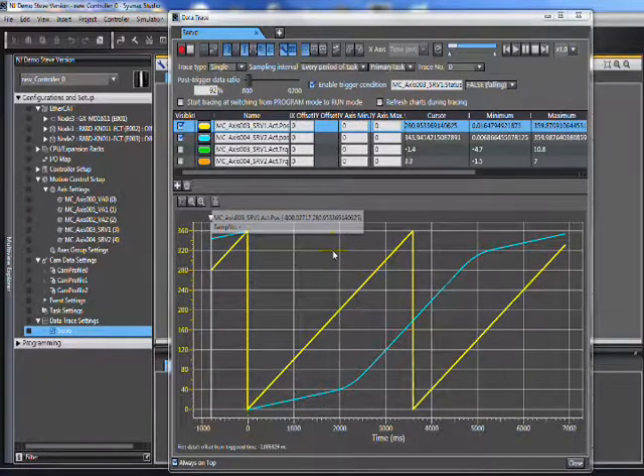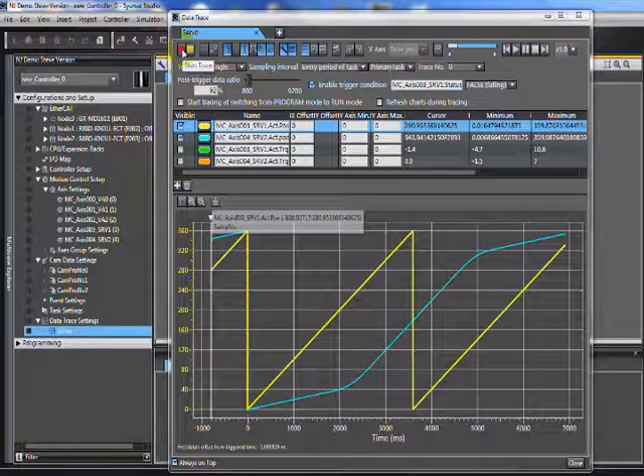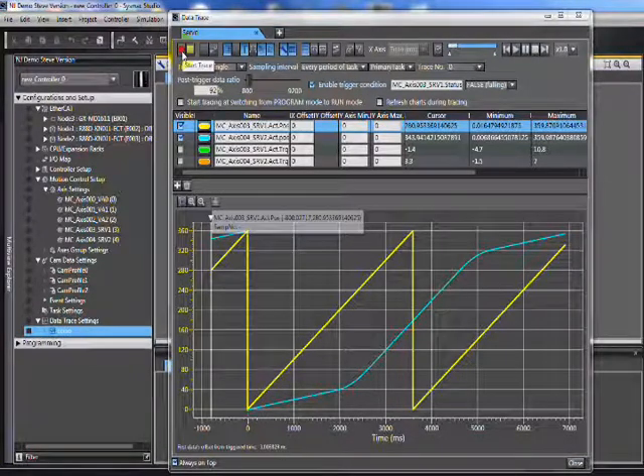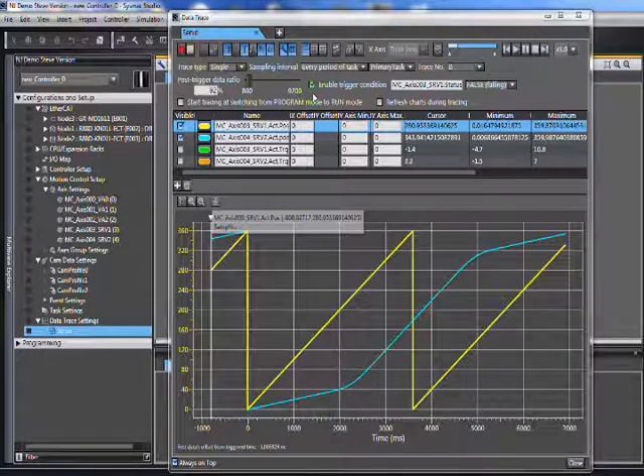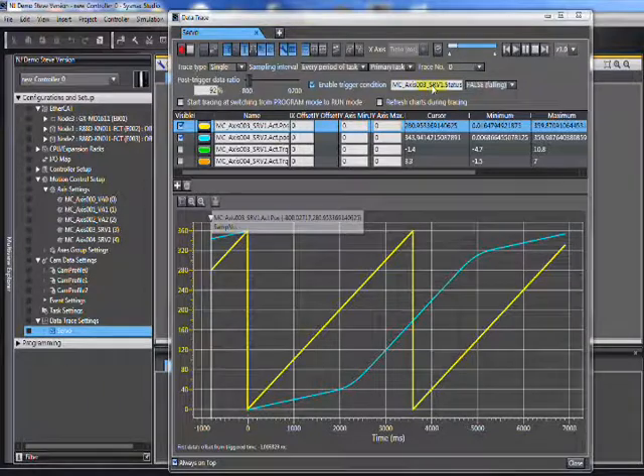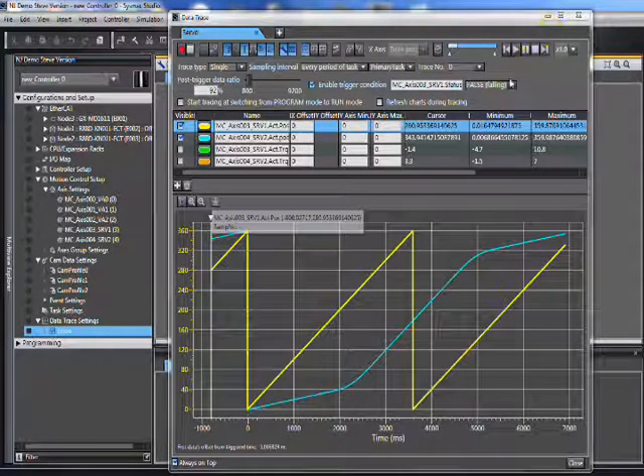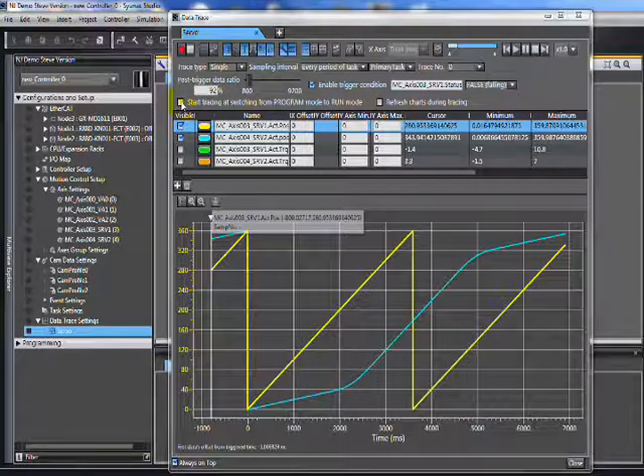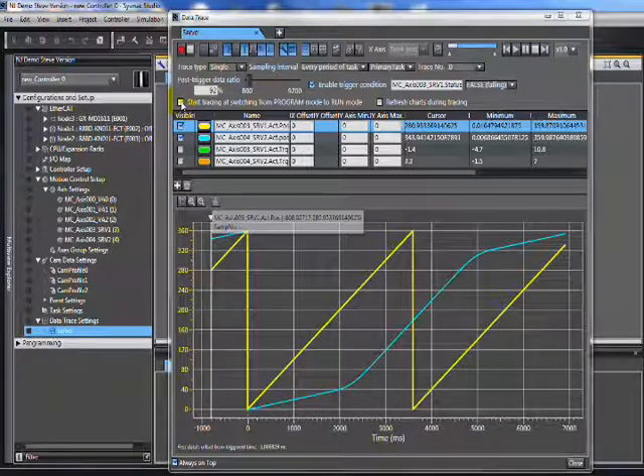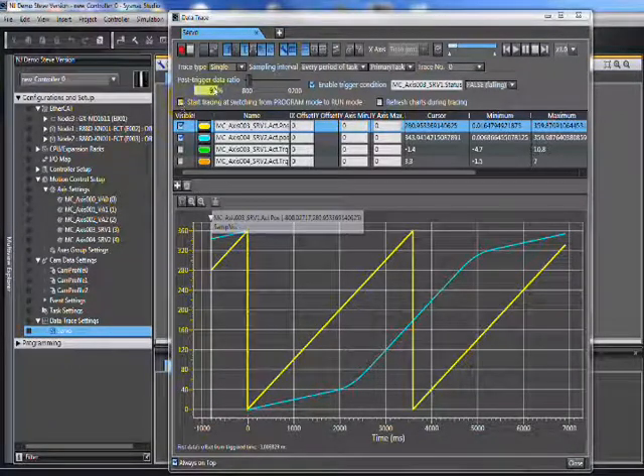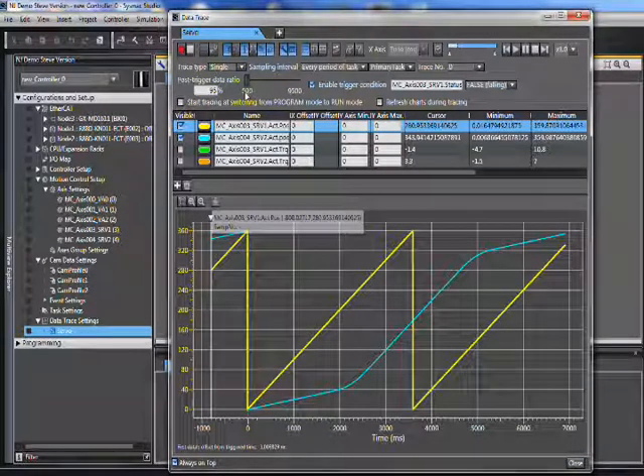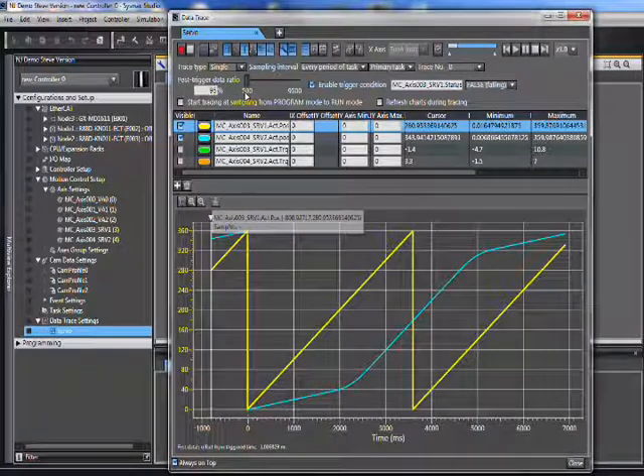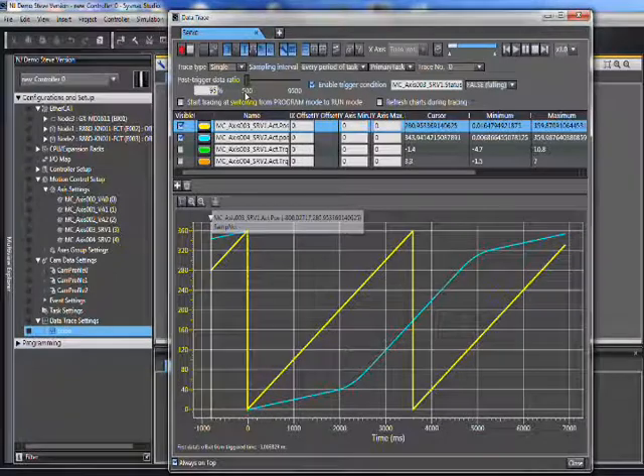The second thing you'll want to know is how to trigger this trace. This is my start — if I don't set up any trigger, this will trigger my trace. I have a couple of other choices: I can turn this bit on and put in some binary bit from within the program and trigger on the rising or falling edge. I can also tell it to start tracing the moment it goes from program to run mode. Those are my three options. The only other real option is right here — I can tell it how many logs before the trigger to keep, so I can see what happened before the trigger event.